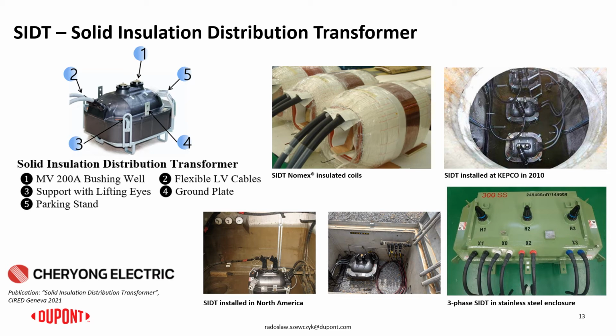The result is the transformer that is insensitive to flooding or submersion in the water. So if we have the case of underground substation and this transformer becomes flooded after heavy rains, it should be able to survive those conditions. And additionally, this transformer offers a high level of fire safety, because neither the winding insulation, the Aramid insulation, nor the polymer compound are flammable. So in case of urban installations, that would be a solution safe for the flooding, but also safe for the fire. And it could be also an alternative design which could be considered for those networks that are now being redesigned for eliminating the risk of the wildfires.